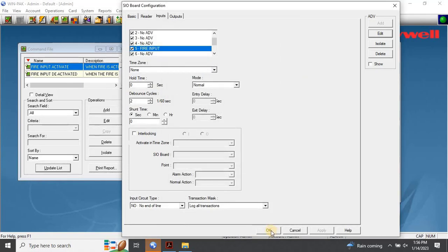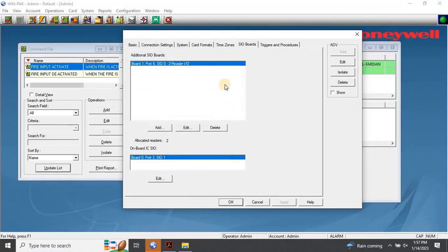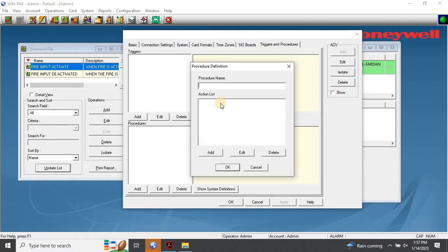The next step is to create the trigger and procedures. To do this, go to the Intelligent Controller Configuration window and select the Triggers and Procedures tab. To add a new procedure, in the Triggers and Procedures dialog box, click on Add at the bottom of the Procedures section. This will open up the Procedure Definition dialog box. Enter a unique and descriptive name for the procedure — for example, Fire Input for Reader 0.